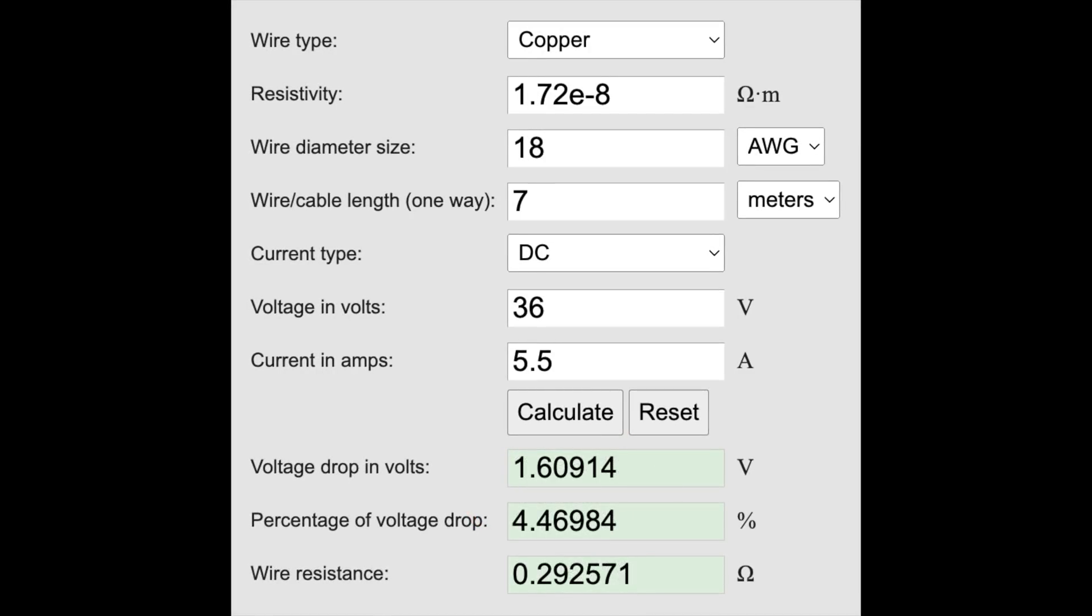Here's what I erroneously used initially, the thinner 18 gauge. Over 7 meters, the voltage drop is 1.6 volts, which is 4.5%, and the reason for the terrible performance.